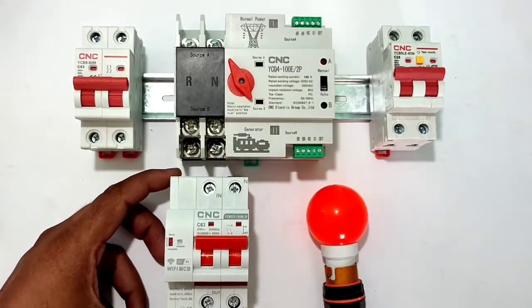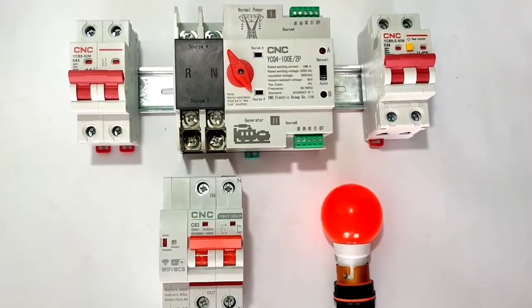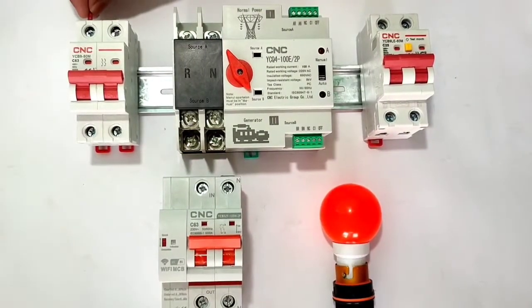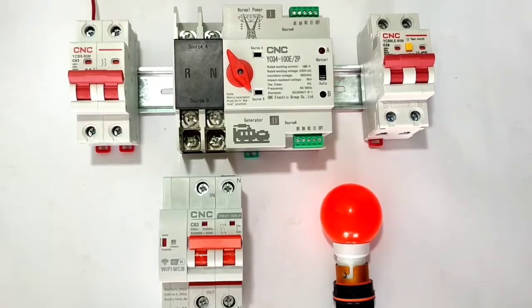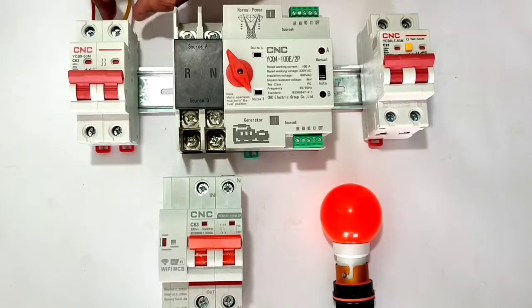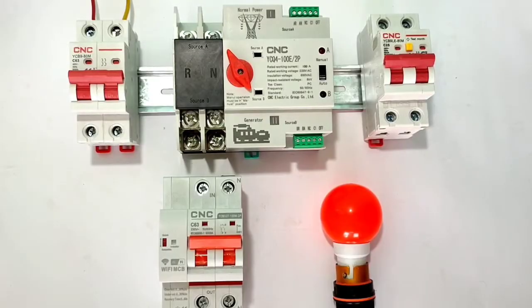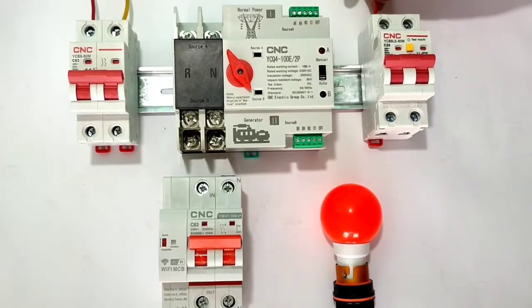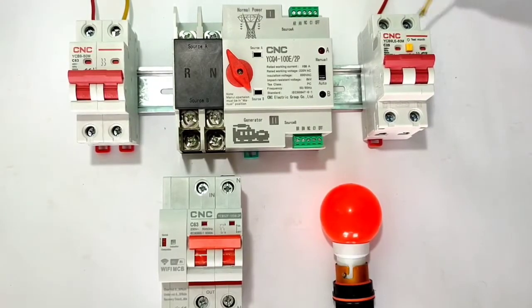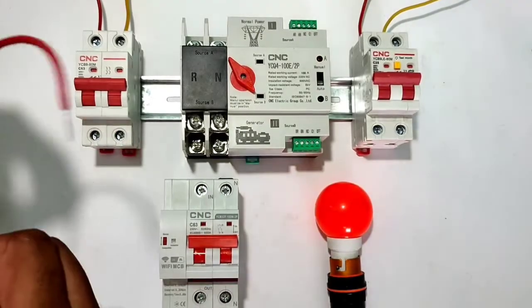So first we connect a phase and neutral wire from the main power supply to the first circuit breaker. You can see here we connect a phase wire to the first circuit breaker, and the neutral wire to the first circuit breaker. Okay, this is our main power supply. And for the secondary power supply, which could be generator power supply or inverter power supply, we connect a phase and neutral here to this second circuit breaker. So our input power supply connection is done.